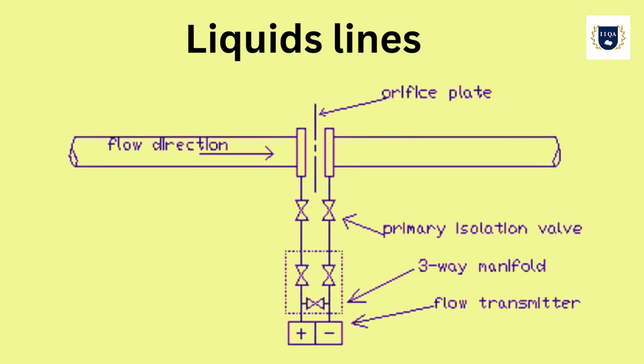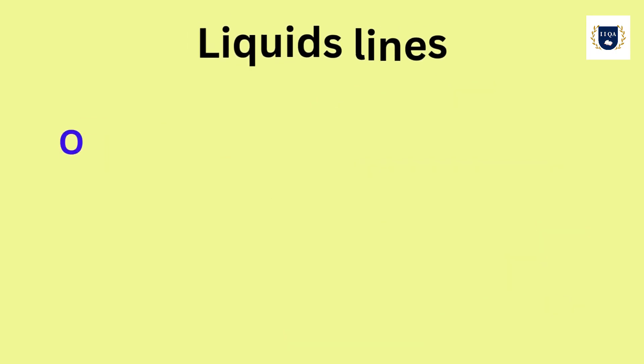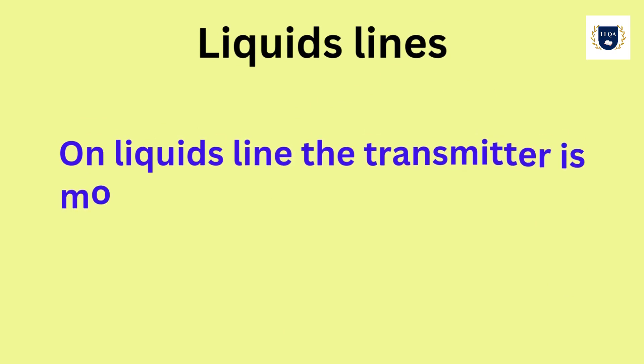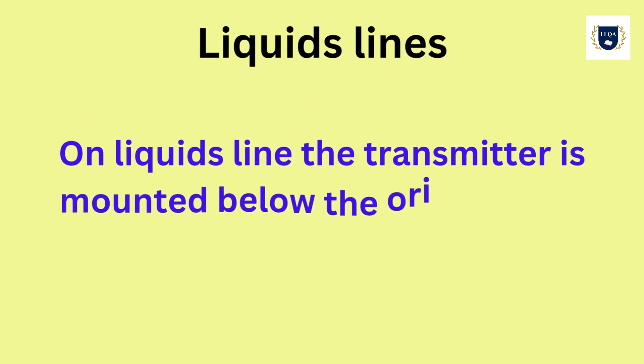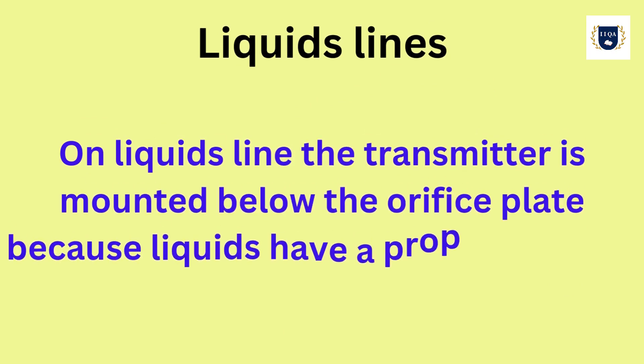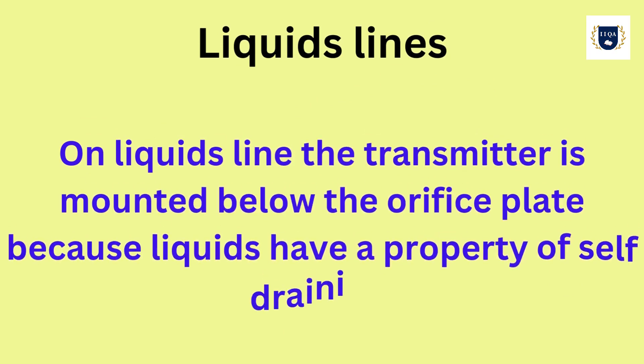Liquid Lines. On liquids line, the transmitter is mounted below the orifice plate because liquids have a property of self-draining.